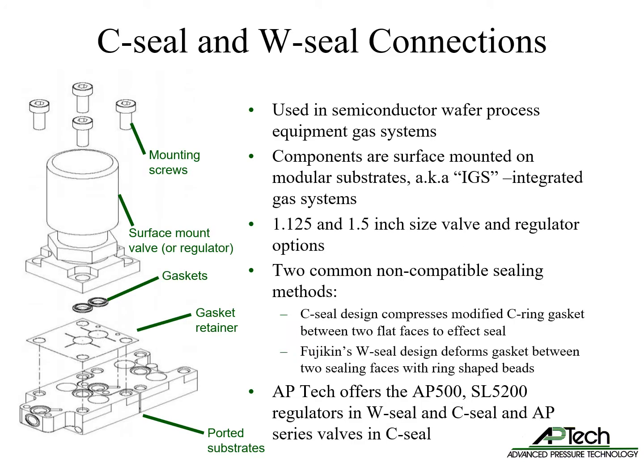Semiconductor wafer process equipment commonly uses surface mount components mounted on modular substrates. These systems are also known as IGS systems or integrated gas systems. There are two size standards: 1.125 and 1.5 inch. There are two common non-compatible sealing methods for surface mount components to attach to the substrates. The C-seal design uses a modified outward-facing C-ring shaped gasket between two flat sealing faces. Fujikin's W-seal design seals by deforming a gasket between two sealing faces with ring-shaped beads.